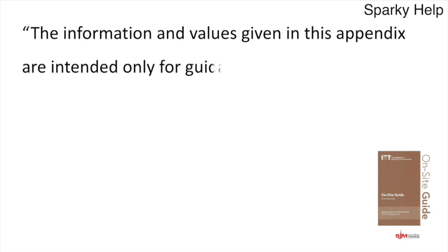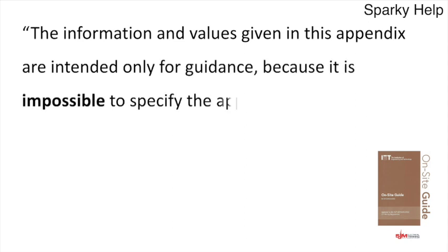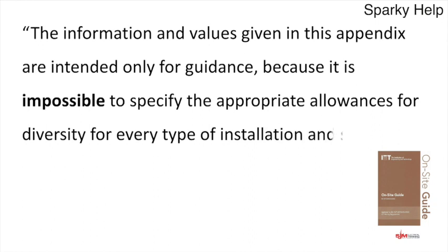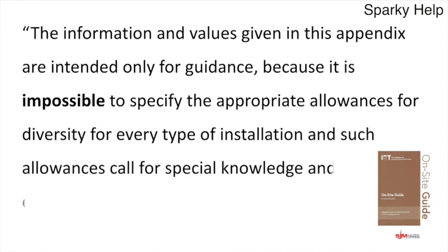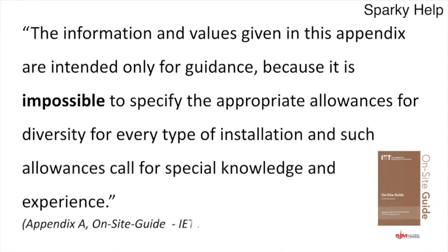Here is what the On-Site Guide says regarding maximum demand: 'The information and values given in this appendix are intended only for guidance, because it is impossible to specify the appropriate allowances for diversity for every type of installation, and such allowances call for special knowledge and experience.' This is from the 2022 version but is the same in all previous versions — the keyword being 'impossible.' So it is very subjective; you're effectively estimating rather than placing a meter over a period of time to record what actually happens.